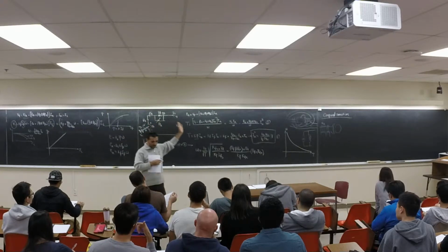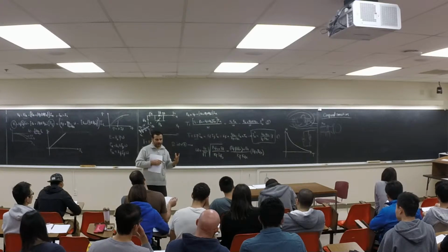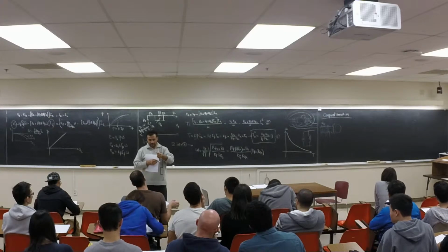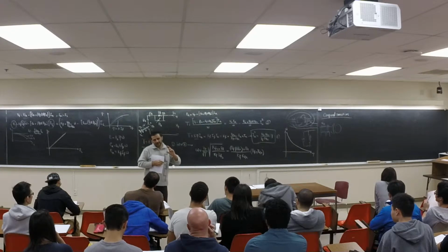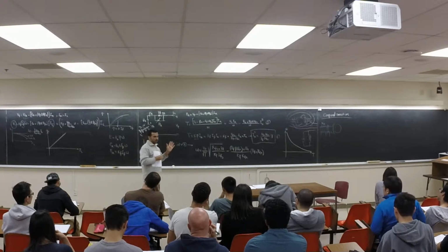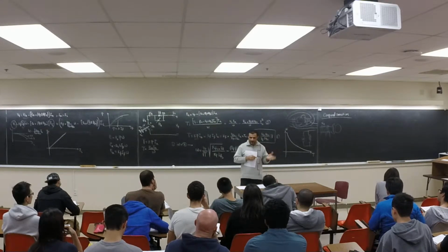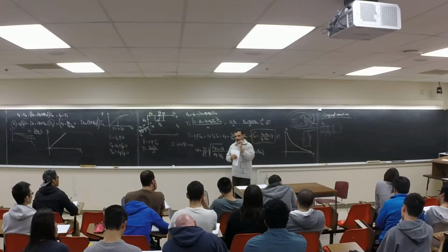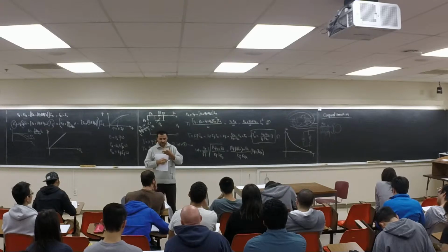Let's see. If you remember, shunt winding is parallel with the voltage, right? The more turns, the higher the resistance. If it's 1 ohm, think about it: you connect it to 100 volts, 100 amps is going to go through the winding. You don't need that much current. You need maybe 1 amp or 2 amps in the shunt winding to magnetize the machine, so you have to have a high resistance. So shunt winding usually has a high number of turns. How about the cross section? Is it big or small? It is small, for higher resistance, right?